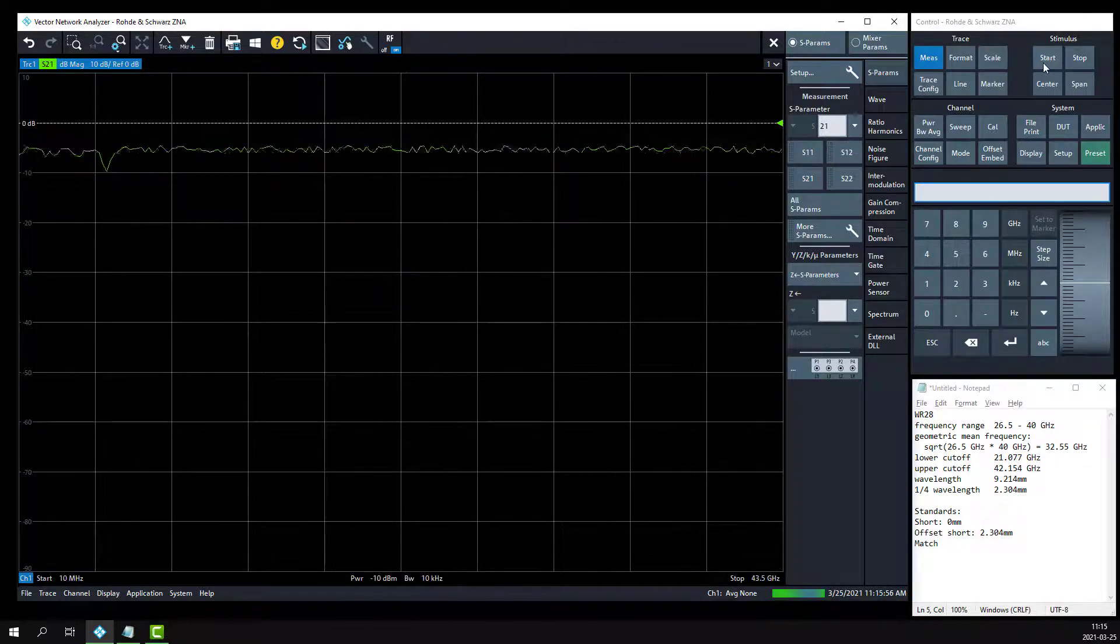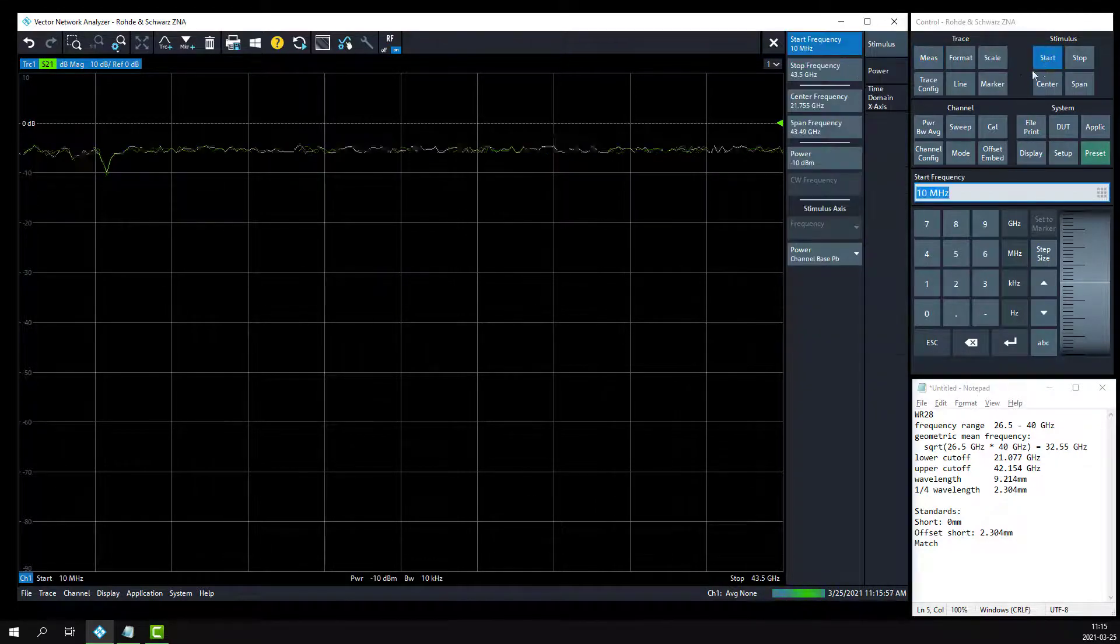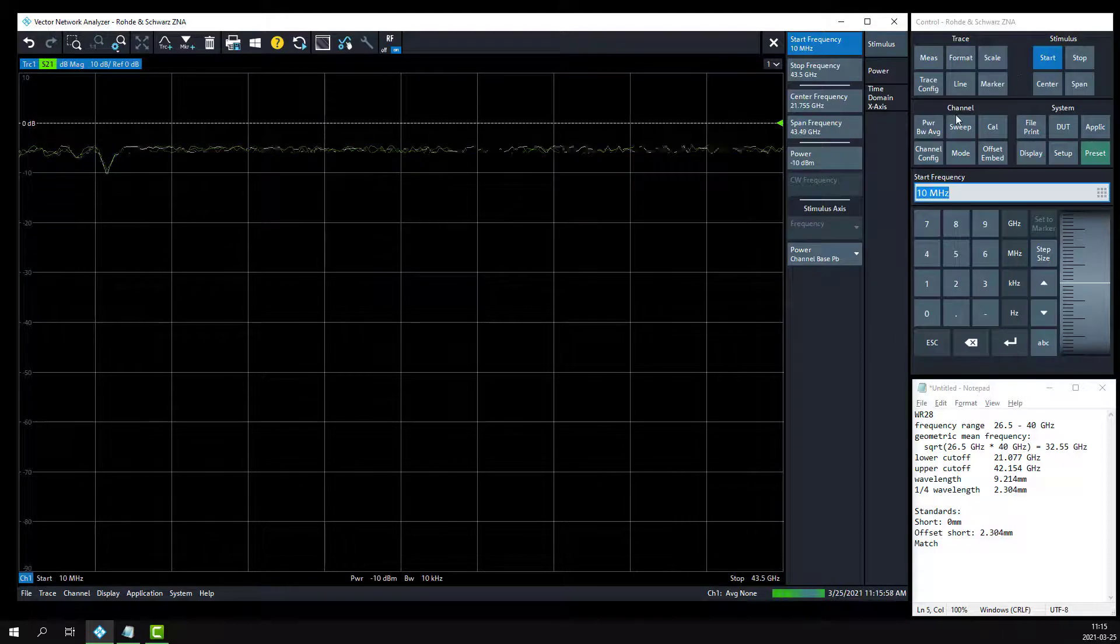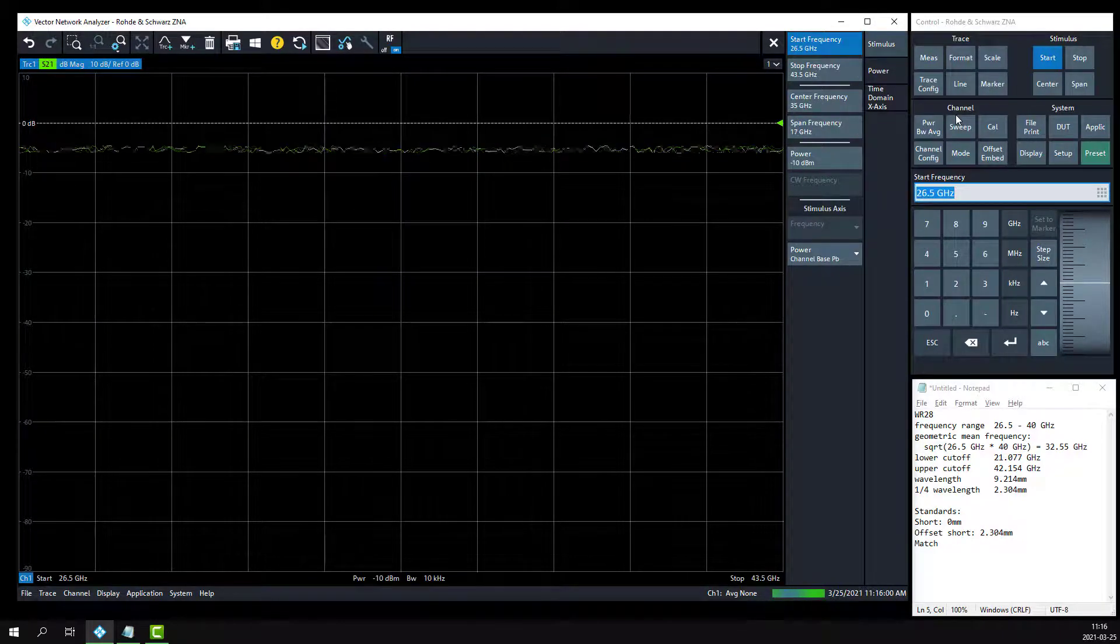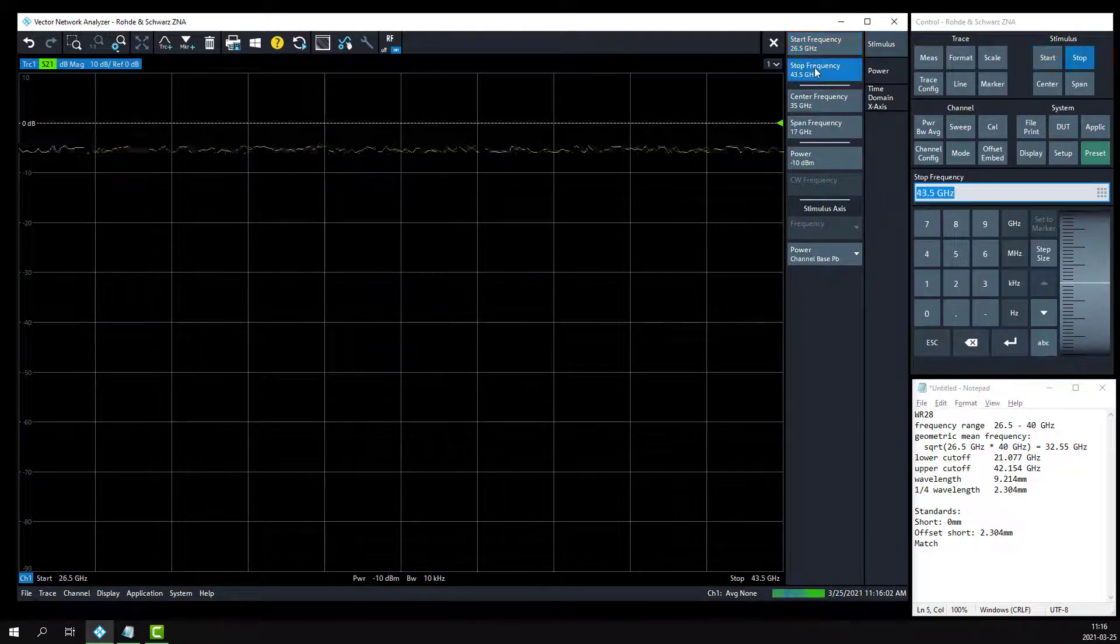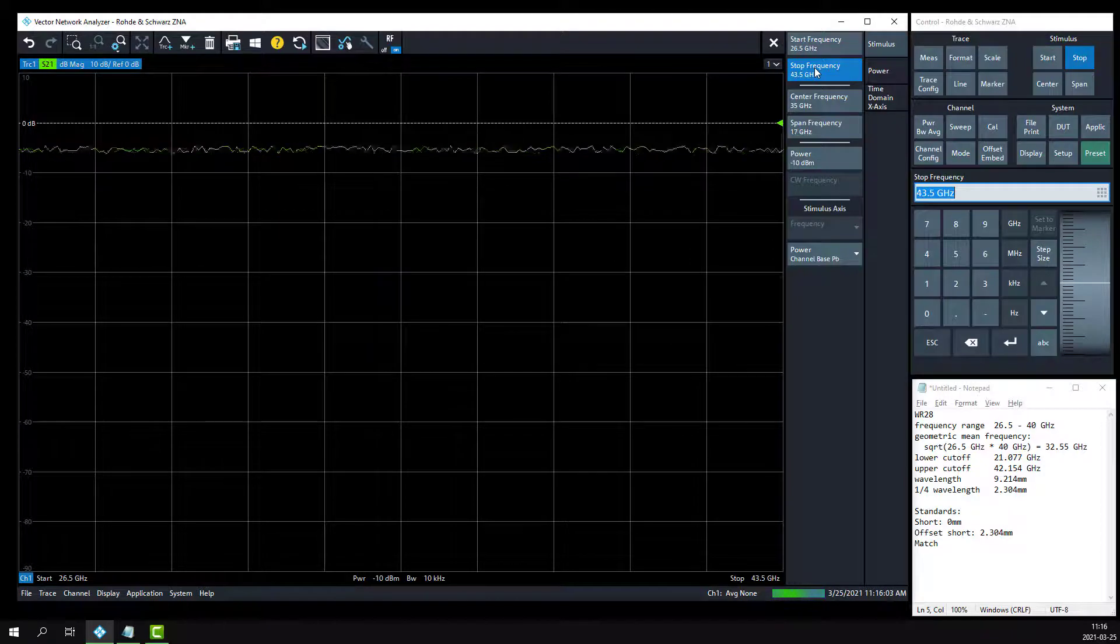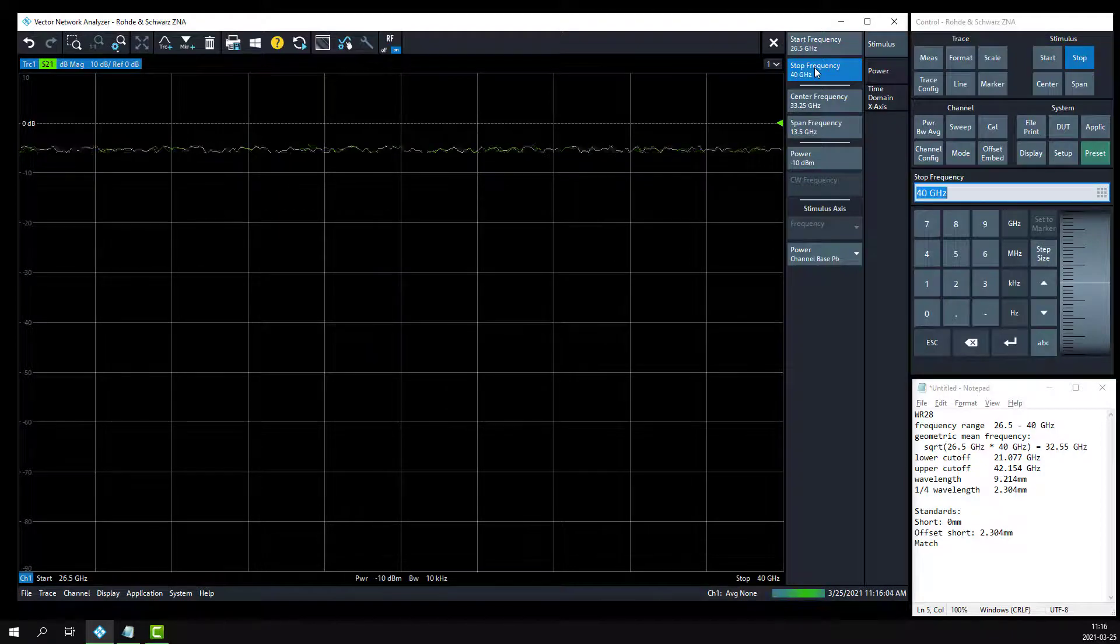First, specify the start and stop frequency within the WR28 waveguide band. Hit the start button, set it to 26.5 gig, and the stop frequency to 40 gig.